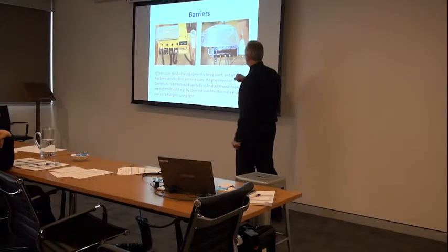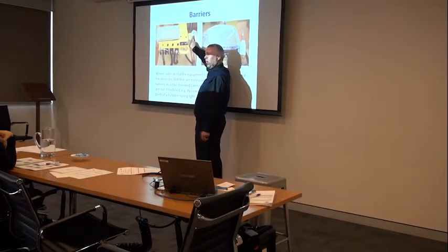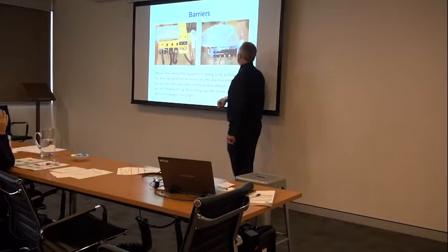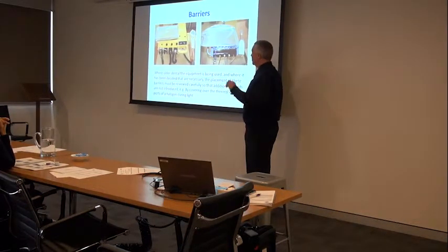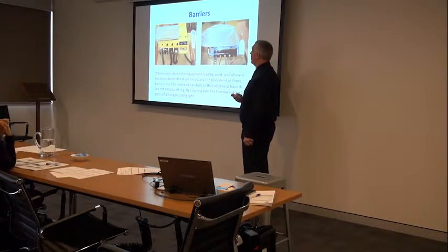Yeah? This was one of my favourites. They put their curing light in a bag. I'm saying, there's a 200-watt lamp in there. That's a ventilation slot. You cover it over, you get a fire. Like, okay, yeah, fair enough. So don't introduce a new risk by bagging something that doesn't need it. Just try to keep a rational head. And maybe you save yourself some time and effort.